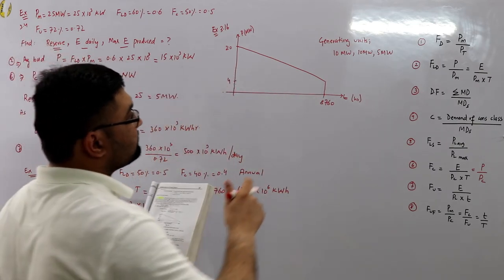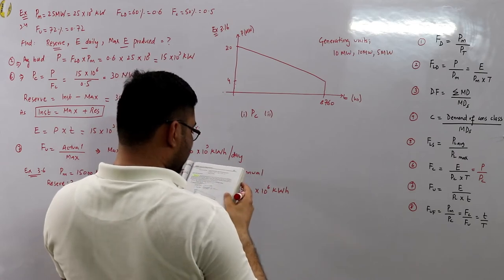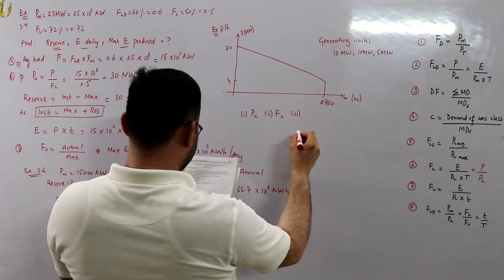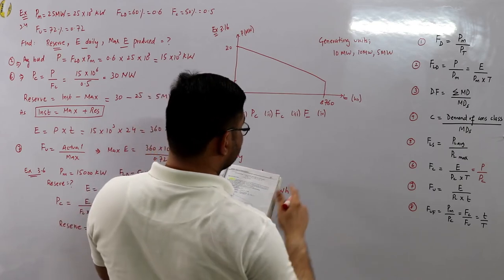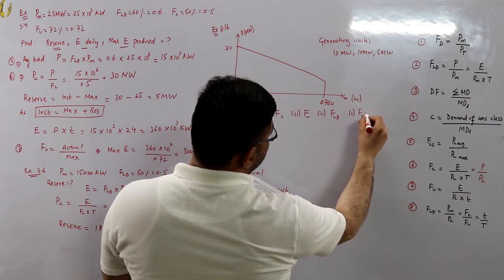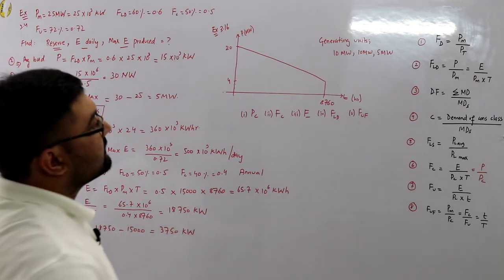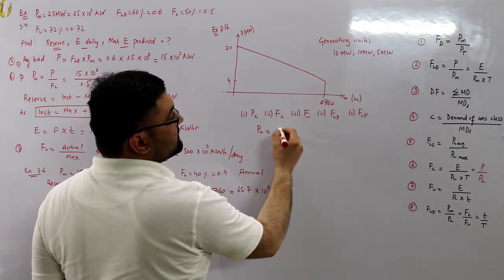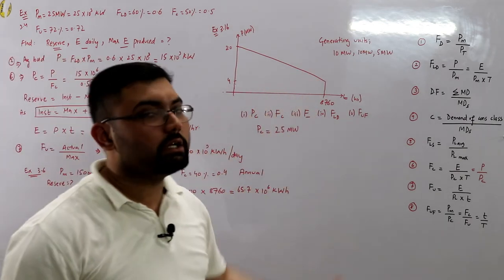Determine: the installed capacity, the plant capacity factor, the units generated per annum, the load factor, and the utilization factor. The installed capacity is the sum of all generating units: 10 + 10 + 5 = 25 megawatts. The average demand P is the average of the two endpoints of the straight-line load curve: (4 + 20) ÷ 2 = 12 megawatts.